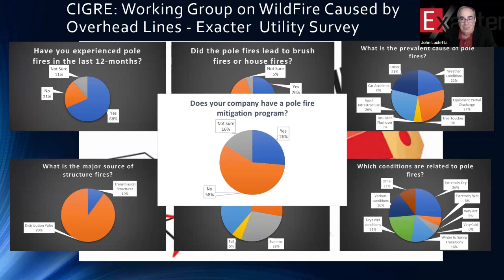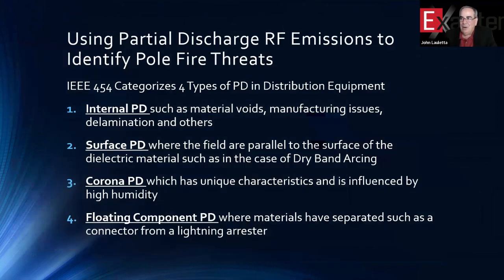Just like there are other avoidable issues with vegetation management, you can reduce or eliminate vegetation outages and so on by proper management of the trees and bushes. But with pole fires, not so much. So I'm part of a number of IEEE working groups and study groups. And in IEEE 454, partial discharge is categorized into 4 specific areas. And partial discharge is an important topic to understand when we're talking about pole fires, because as you remember, deteriorated equipment was a large contributor to a pole fire situation.